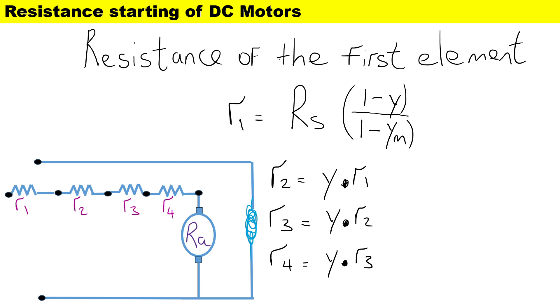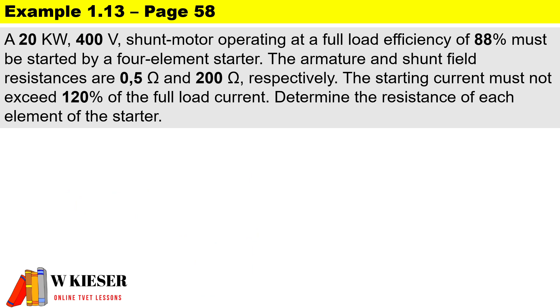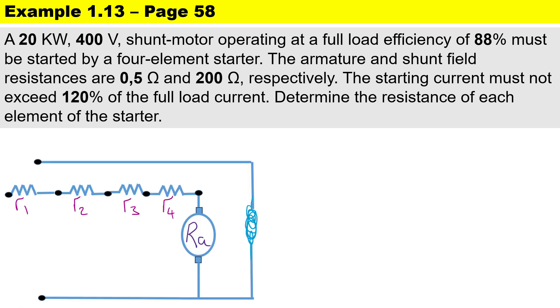In Example 1.13 on page 58 of our textbook: a 20 kilowatt, 400 volt shunt motor operating at full load efficiency of 88% must be started by a four-element starter. The armature and shunt field resistances are 0.5 ohms and 200 ohms respectively. The starting current must not exceed 120% of the full load current. We need to determine the resistance of each element of the starter, shown here with four elements and five studs to limit current at start.